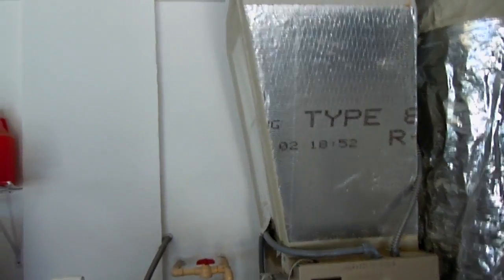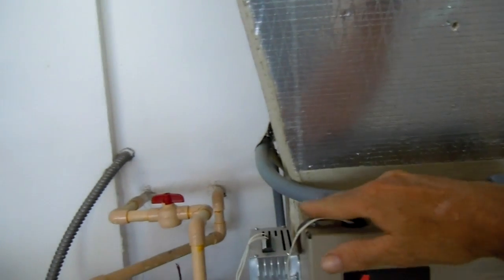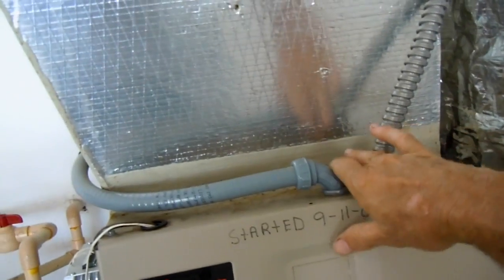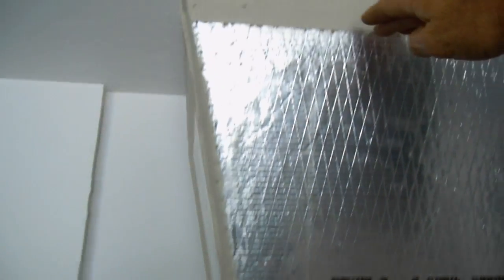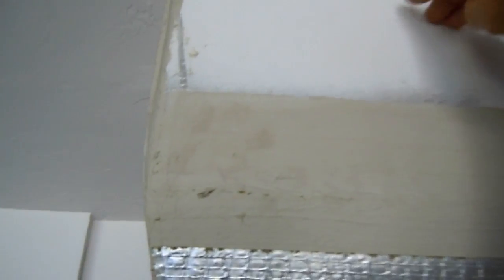You're supposed to make sure that you have a minimum of three feet from your supply end of your air handler, up your plenum, to where you're going to make your hole. You should have at least three feet.